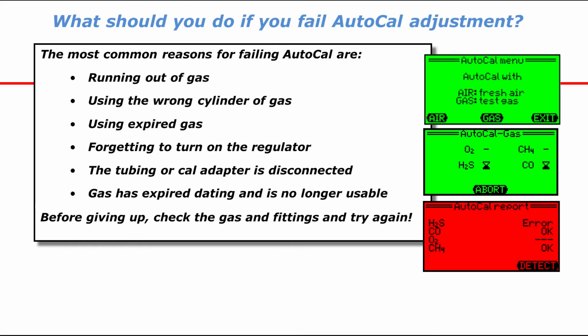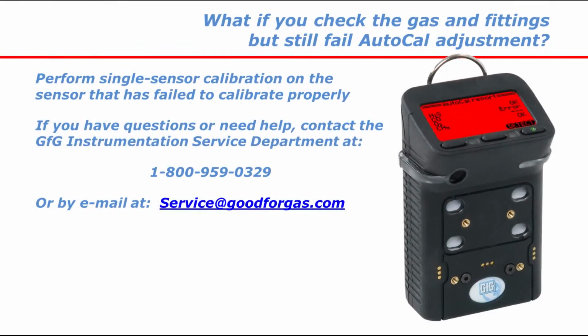Check to see that you have the right cylinder of gas, that the gas is not expired, and that the fittings are properly connected. Then repeat the autocal procedure. When only one sensor fails, the problem may be with the sensor. In this case, you will need to perform a single sensor calibration.